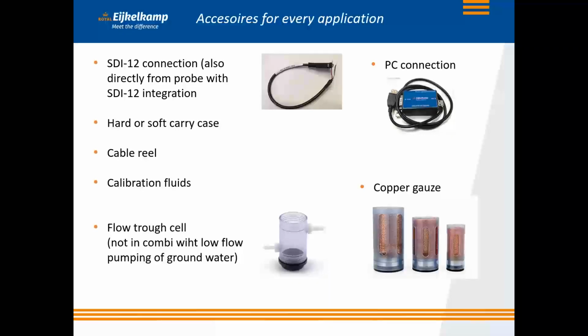The first one is the SDI12 connection, used for RS232 to SDI12. In the probe itself, SDI12 can be put on the computer board, but that must be chosen as an extra option for the probes — standard is a probe without SDI12. The SDI12 connection will be delivered with open ends, or together with a connector, just as you want.